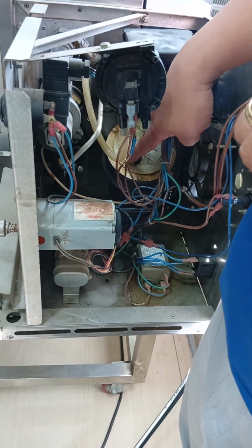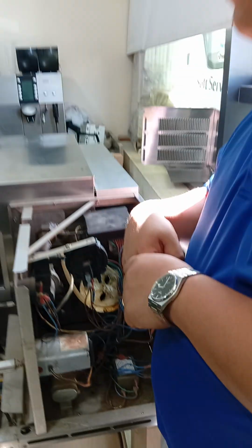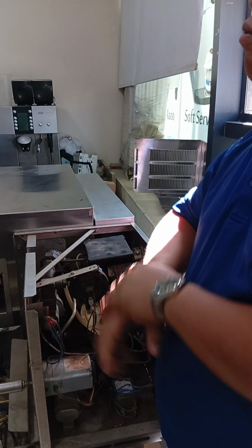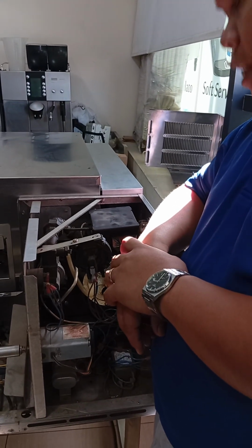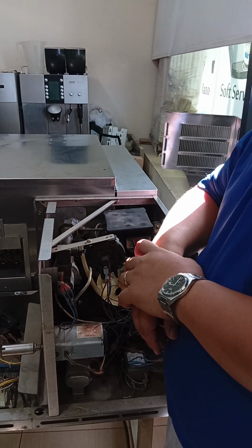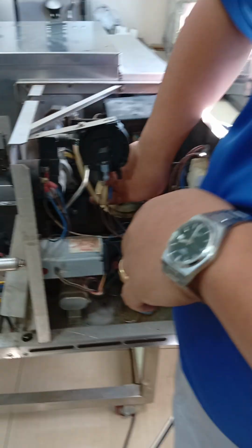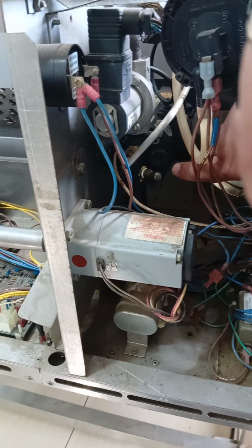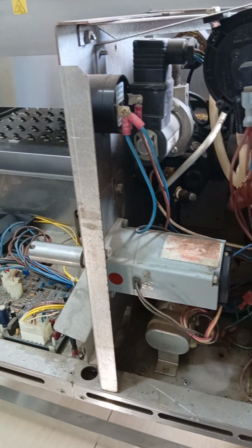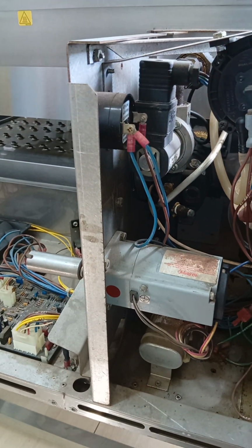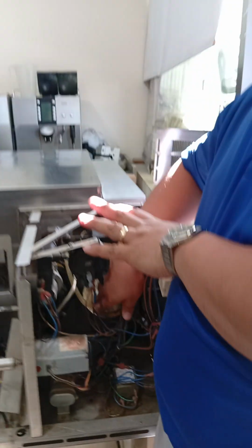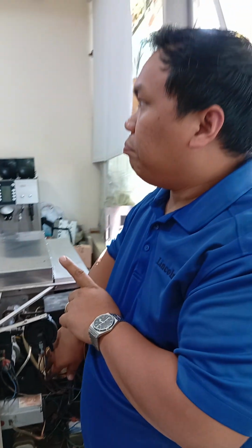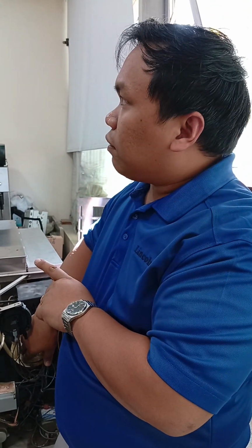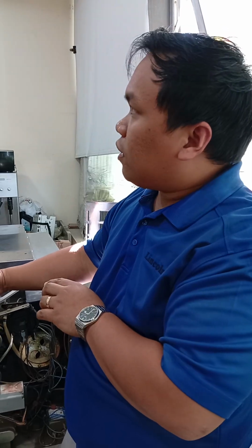Then check the radial inside, how clean, and then dismantle. So it means it has to be open. Yes. All right. What about the burner? For the burner, you can open. I will not recommend opening it on a monthly basis. Once every 3 months, you open one time, then you maintain. After 6 months, if you have a contract, then open again. So it's just like twice a year. It has to be inspected.